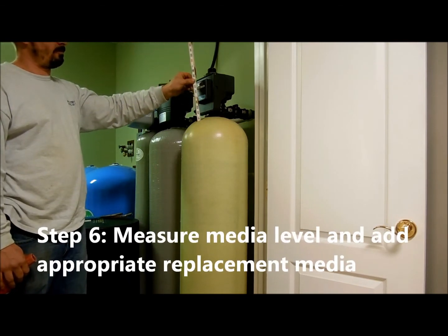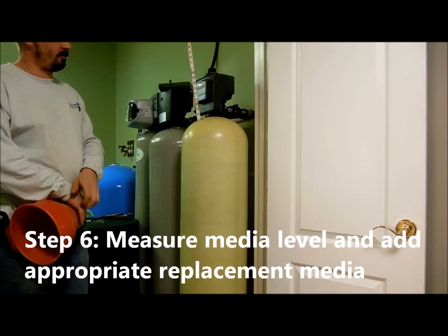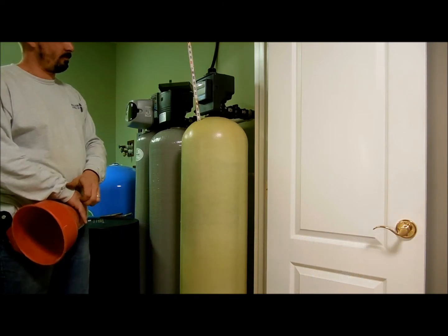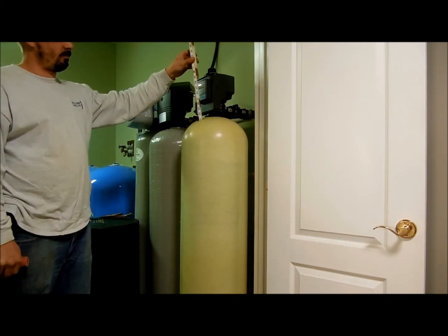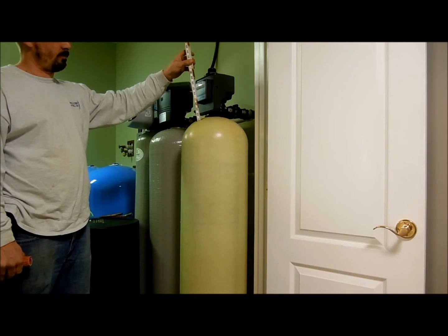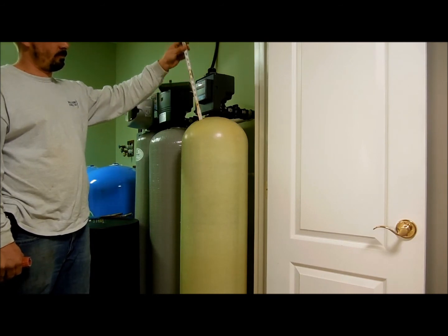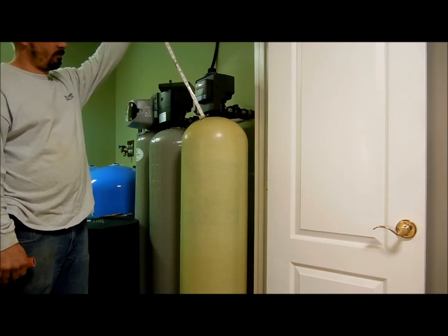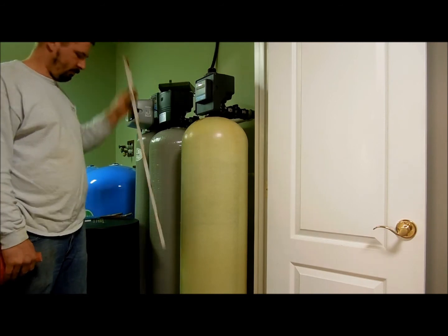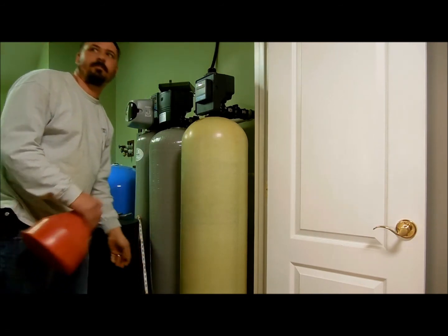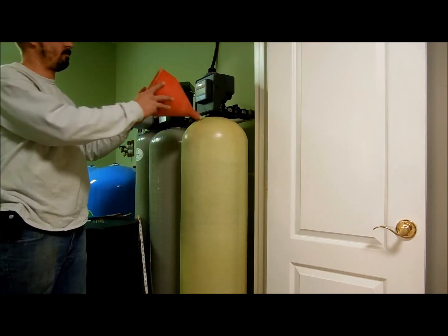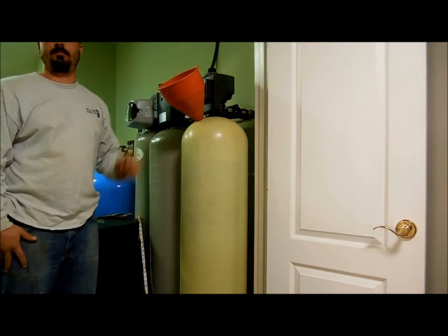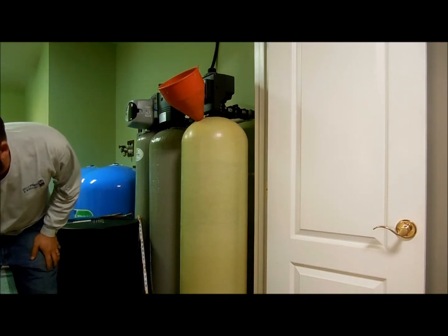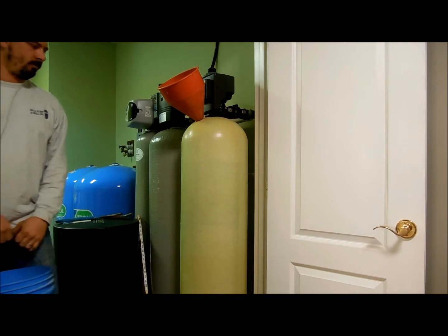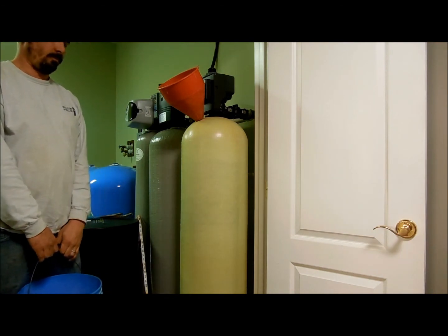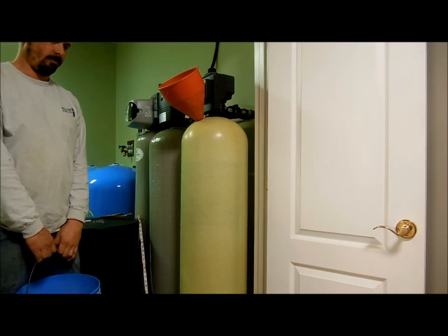Once the fill port is off, you need to have a measuring tape or yardstick to see how far down the calcite bed is. Remember, calcite doesn't need changed. You just need to add more each service to bring it up to the appropriate level. We try to only fill the tanks to within 20 inches of the top. This allows room for when the filter backwashes for the calcite to be fluffed or broken up without lifting up so high that it gets into your plumbing.